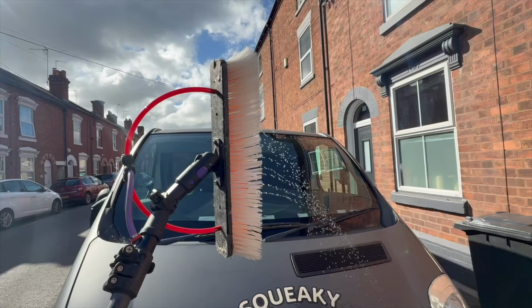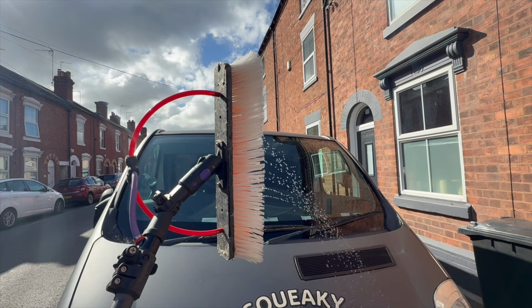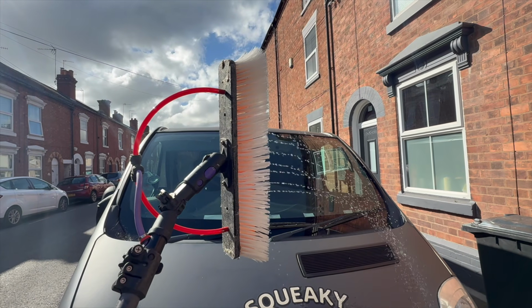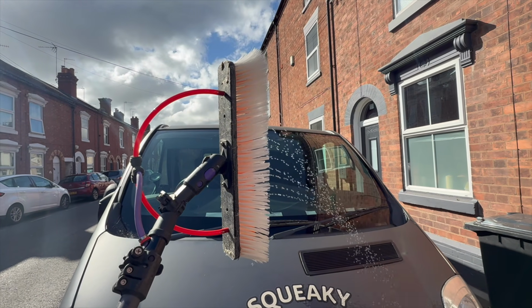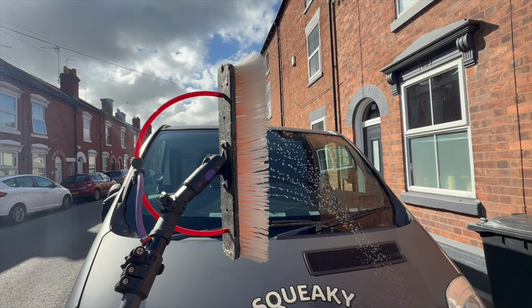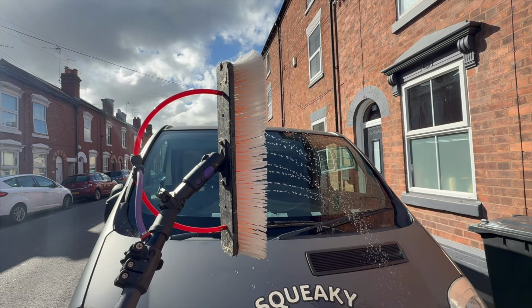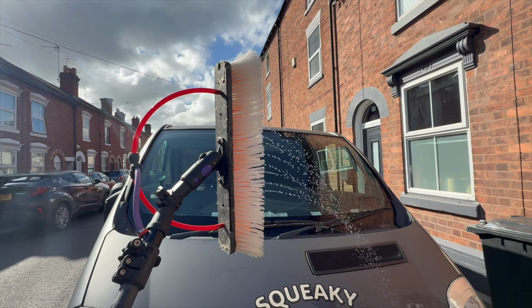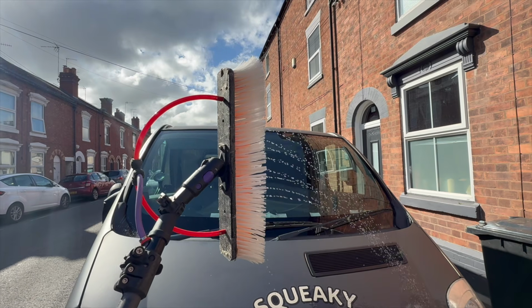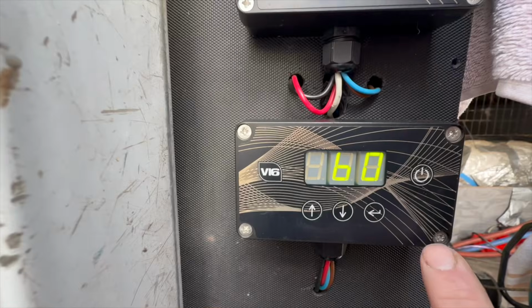Right. So what do you get if you set your dead end too low? Well now then you've mentioned already that the water jet pulsing. So it seems to sort of stop and we get this kind of wave. And what that is the controller going, oh, I need to turn the pump on. Oh no, I don't. I need to turn the pump on. Oh no, I don't. And it just means that the calibration value is too low. The controller is, in effect, cycling the pump on and off.